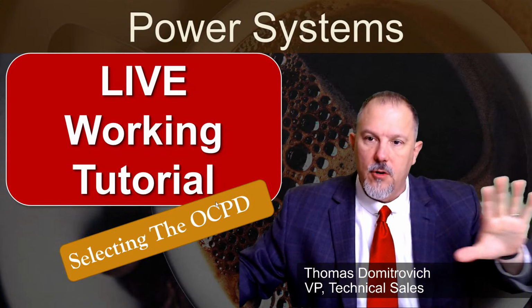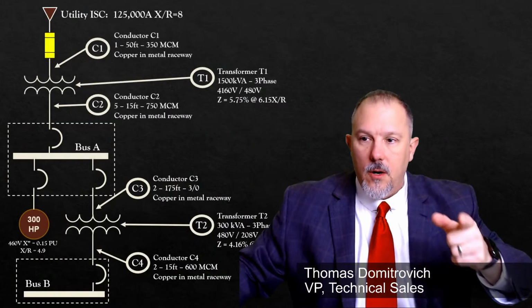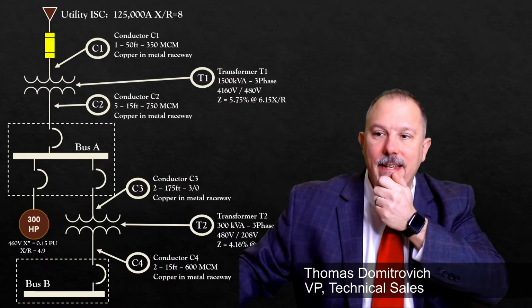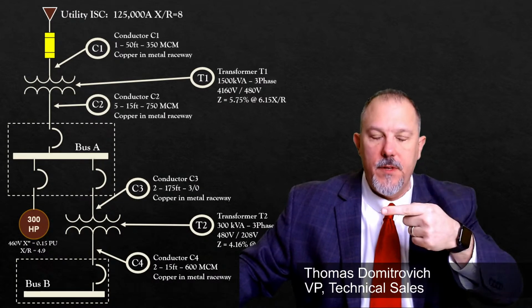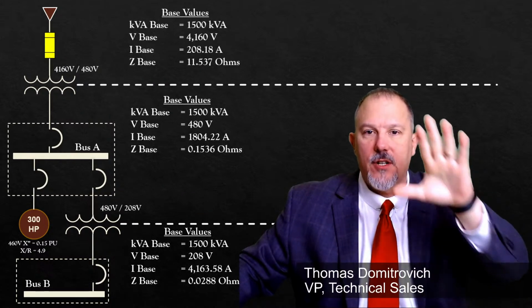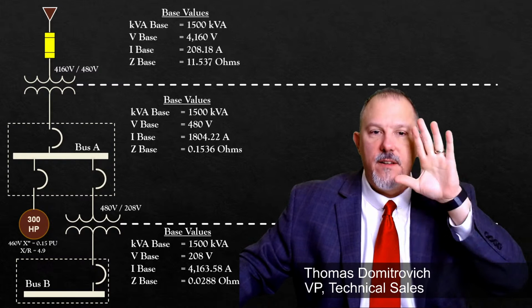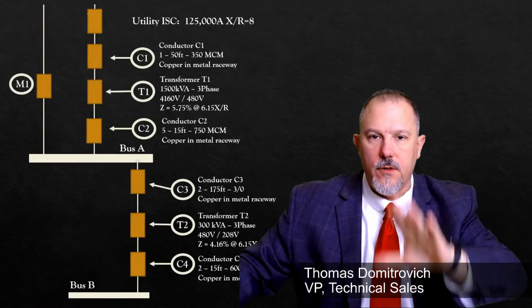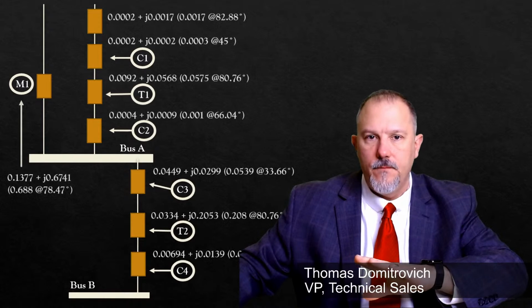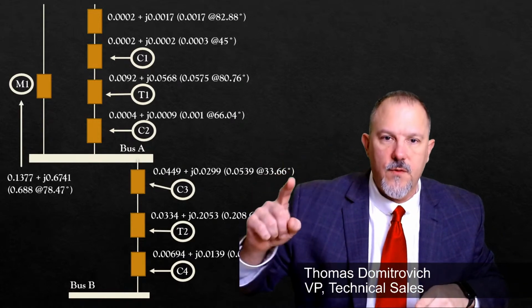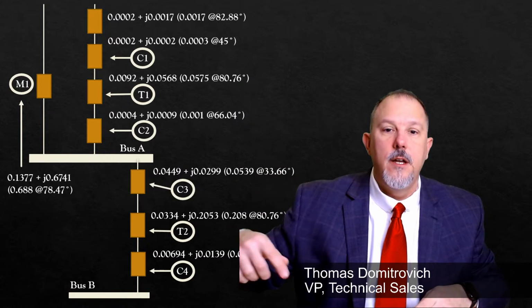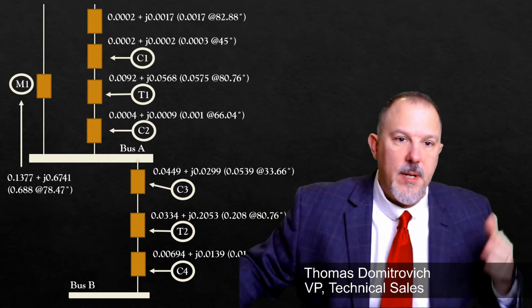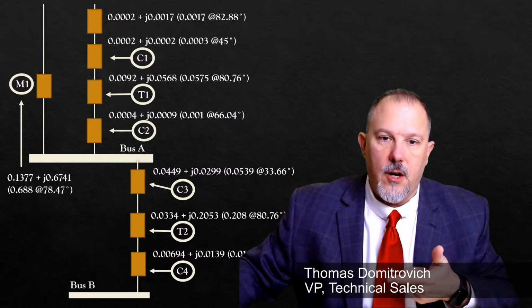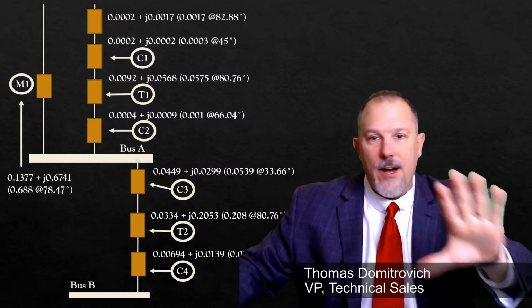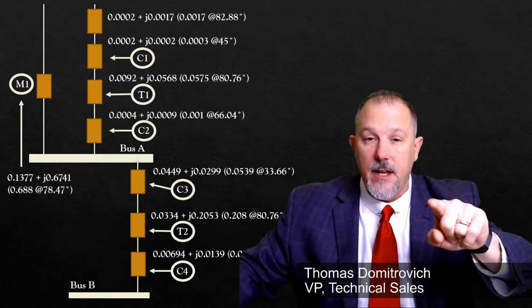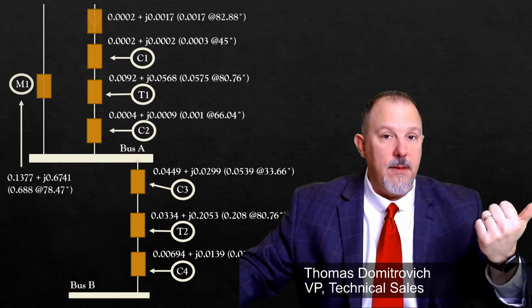So I got SKM open over here. If you recall, this was our one line. We basically established our per unit, and we converted all of our components over to an impedance value. So we've got the utility, the transformer, utility, conductor, transformer, conductor, conductor, transformer, conductor. We have bus A and bus B. We've got motor contribution on bus A. And we went through how we came up with these values, and we calculated the fault current at A and B by hand, compared that with SKM.